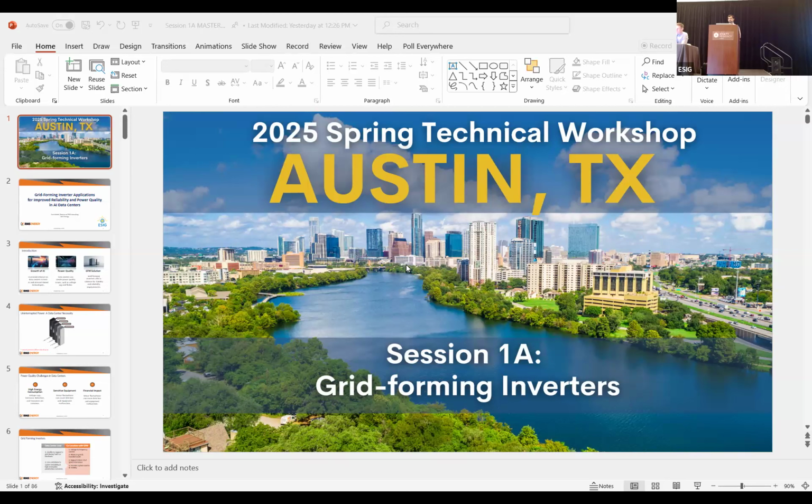There is, of course, the other option that is there, which we'll talk about. But just the placement of this battery with advanced grid support, even though when you look at it by itself, it shows a much better resistance characteristic, what the type 3 wind is seeing is it potentially sees a lower resistance, which means that the oscillation could be much more. The impact of the resonance could be much more, and that's precisely what we see. We see instability cropping up in the orange curve. It's a bifurcation cropping up that happens with the advanced grid support coming in.